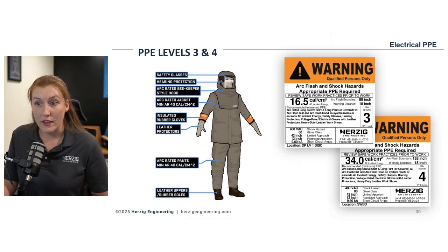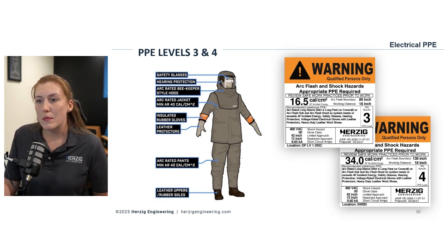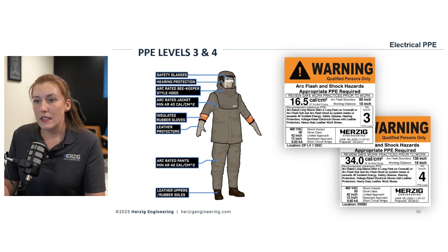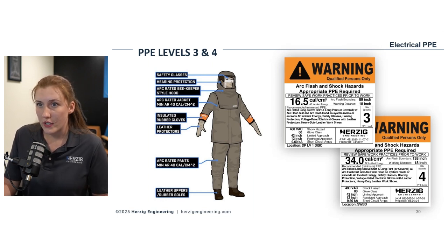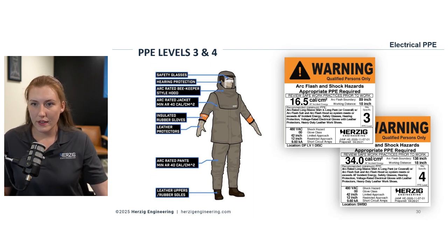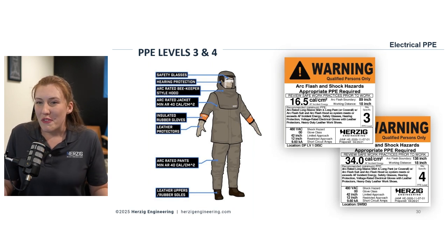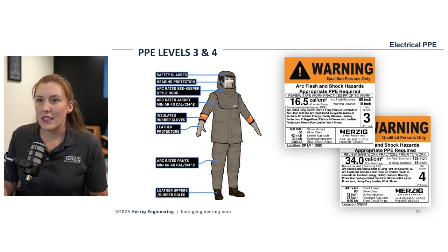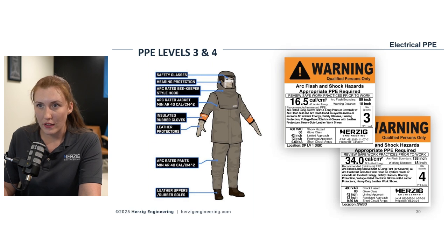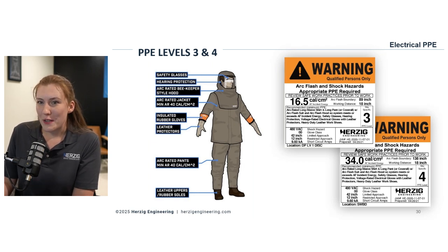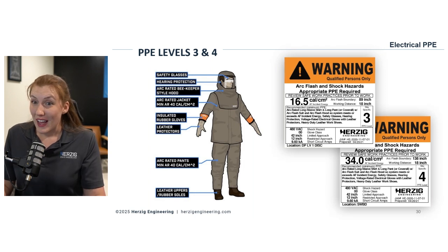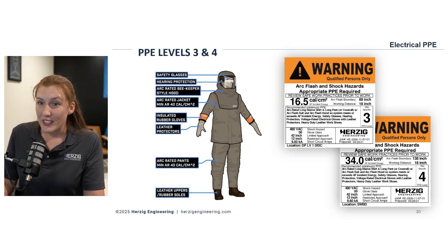There's also shock hazards. I can't tell you the number of times I've seen people talking about insulated gloves and leather protectors as part of the arc flash PPE. Now, they do provide arc flash protection, but those insulated gloves are primarily for shock protection. So let's be clear - even if there's not an arc flash hazard, you could still have a shock hazard. You've got to have your insulated gloves with protectors on regardless.